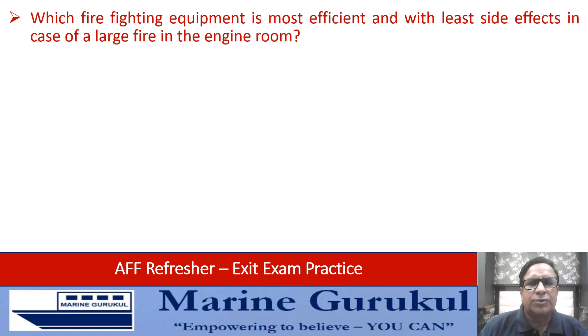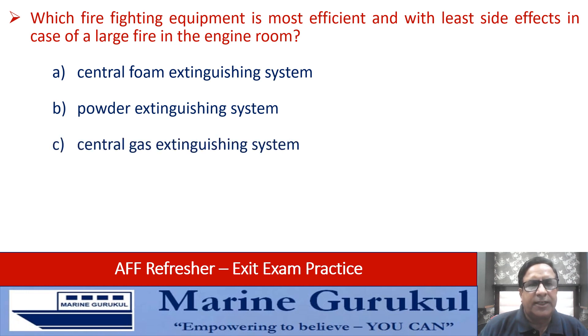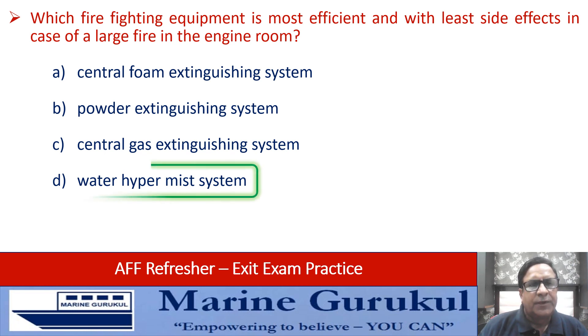Which firefighting equipment is most efficient with least side effects in case of a large fire in the engine room — central foam extinguishing system, powder extinguishing system, central gas extinguishing system, or the water hypermist system? The most efficient with least side effect is the water hypermist system because of its cooling effect and conversion to vapors. The hypermist system is the most efficient for the engine room.